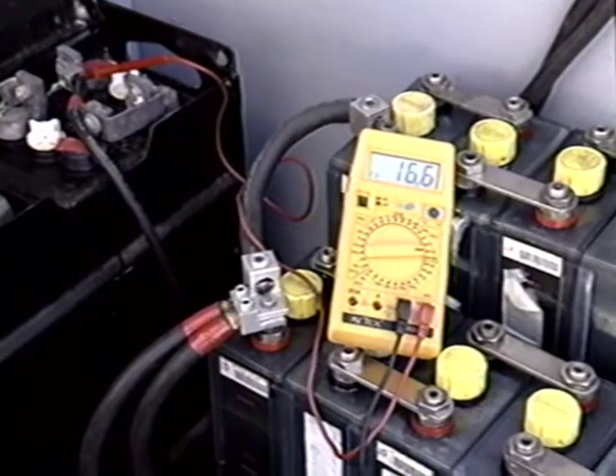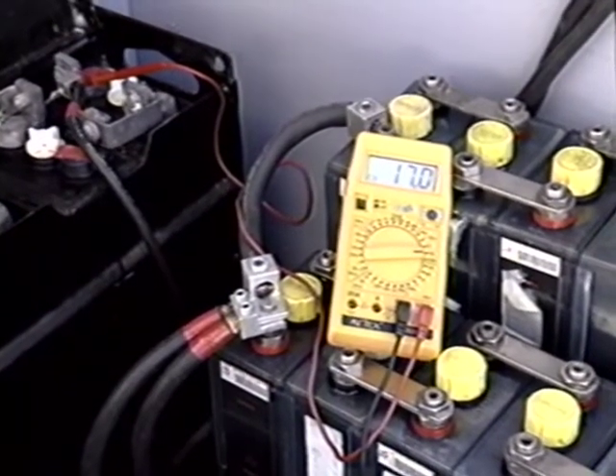Another important thing about battery maintenance is providing a periodic equalization charge. By an equalization charge, we mean a regular controlled overcharging of the batteries to bring all of the cells up to their proper specific gravity. In this case here, we've got a 12-volt battery bank. We've got it hooked up to this meter here, which is giving us a very accurate reading of battery voltage. Up at 16.5 volts. This means that the batteries are up at a full state of charge, and we're now providing a little bit of equalization charge to them to try and make sure that we're going to reduce any sulfation building up on the plates. This is something we want to periodically do with lead-acid batteries so that they'll last as long as possible.